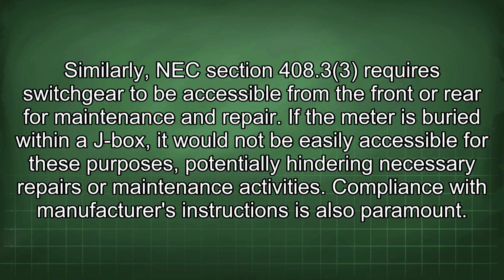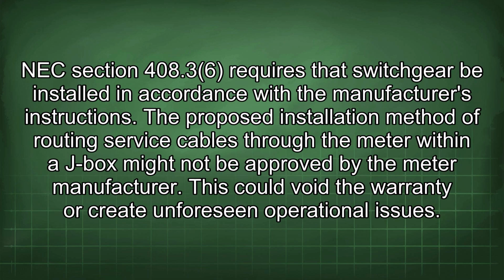repairs or maintenance activities. Compliance with manufacturer's instructions is also paramount. NEC Section 408.3(6) requires that switchgear be installed in accordance with the manufacturer's instructions. The proposed installation method of routing service cables through the meter within a J-box might not be approved by the meter manufacturer. This could void the warranty or create unforeseen operational issues.